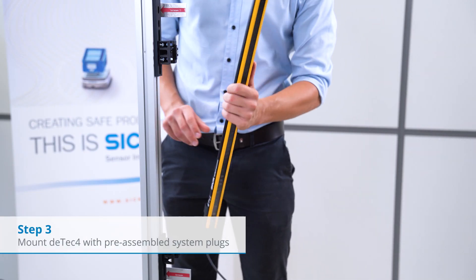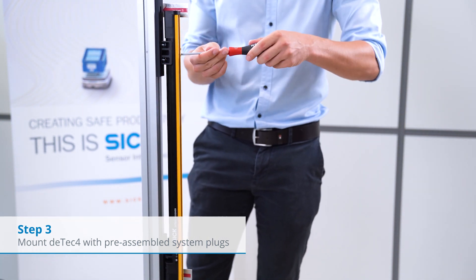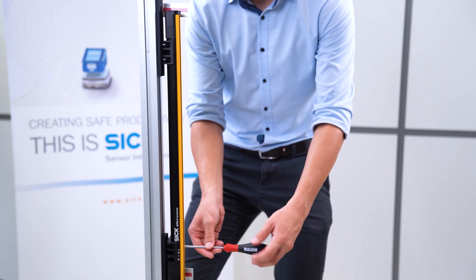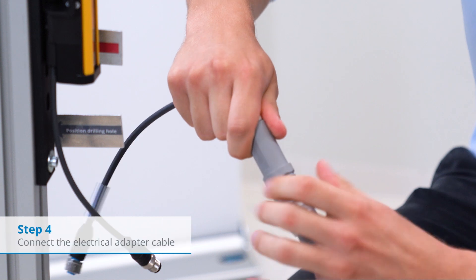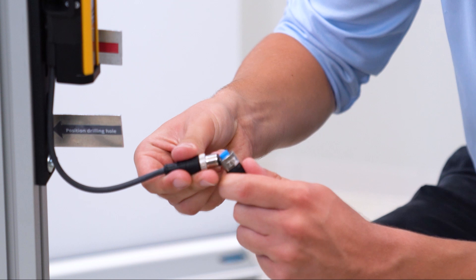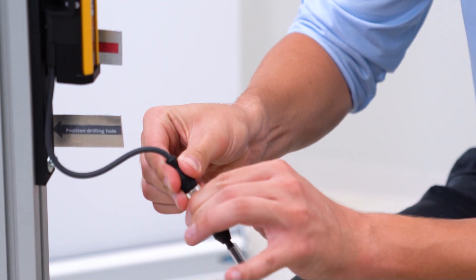Afterwards, we mount the deTec4 including the system plug, which has been already pre-mounted. Just twist the device inwards and tighten the screws of the FlexFix brackets a bit. The next step is the connection of the electrical adapter cable. This cable transfers the required pinning correctly from the old M23 12-pin connection to the new M12 5-pin connection.